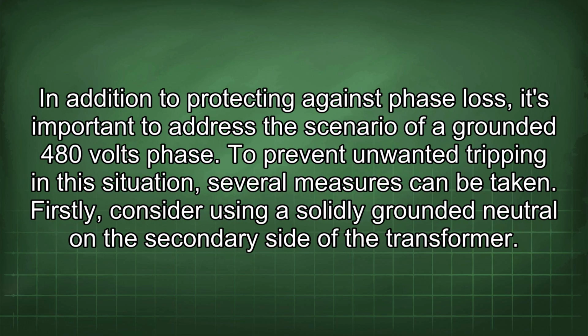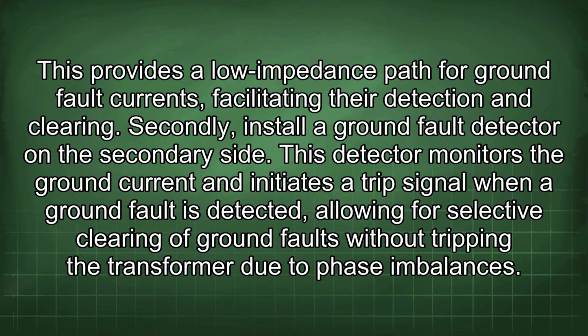In addition to protecting against phase loss, it's important to address the scenario of a grounded 480 volt phase. To prevent unwanted tripping in this situation, several measures can be taken. Firstly, consider using a solidly grounded neutral on the secondary side of the transformer. This provides a low impedance path for ground fault currents, facilitating their detection and clearing.